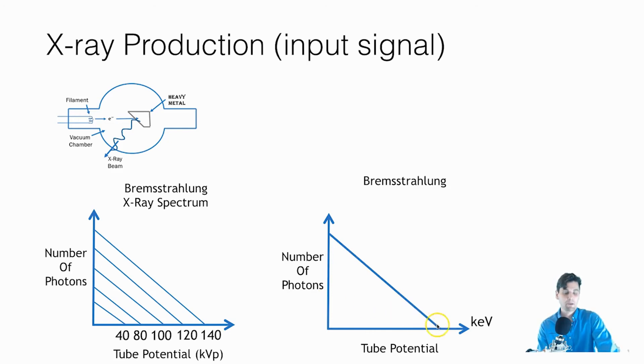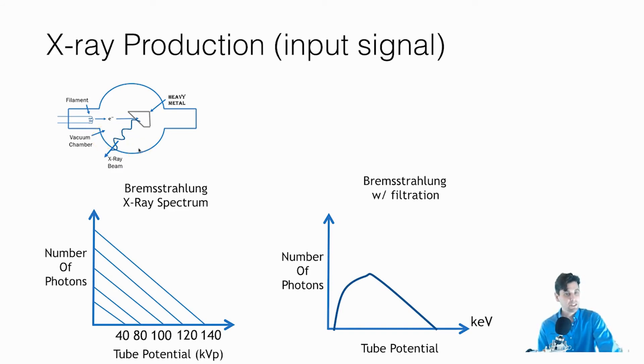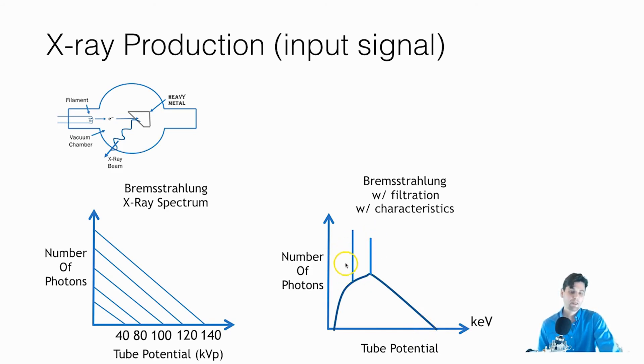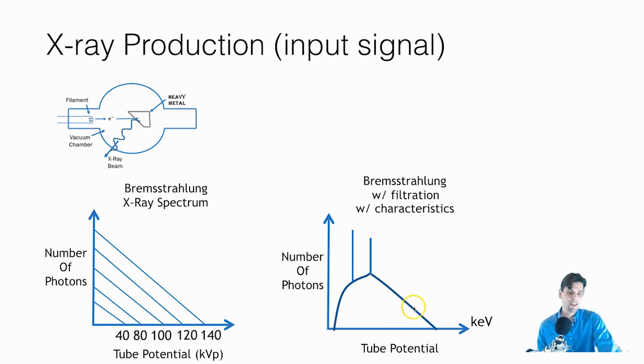In reality, what happens is we start with that Bremsstrahlung spectrum and then apply filtration — the x-rays pass through the glass window and usually additional filtration before reaching the patient. Those lower-energy x-rays are preferentially attenuated. So you get a filtered Bremsstrahlung curve, and when you add the characteristic peaks, you get the classic x-ray spectrum shape. When someone shows you a plot of energy versus number of photons and talks about the x-ray spectrum, it's not really that complicated — there are just two fundamental things happening: Bremsstrahlung and characteristic radiation.